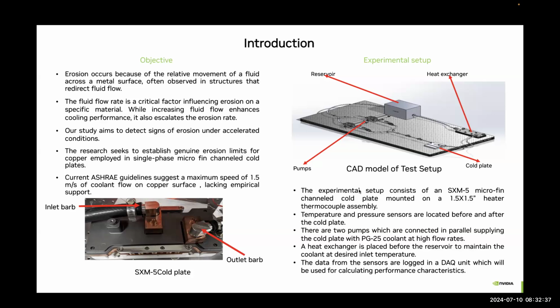We developed an experimental setup. We started with a small setup with one cold plate, using pressure sensors across the cold plate and temperature sensors to measure its thermal resistance. We made sure that in this entire setup everything is made of stainless steel except the cold plate. We ran this setup for five months in total. To look into copper content, we take a sample every month and send it to labs for testing to see if there is any copper content increase.